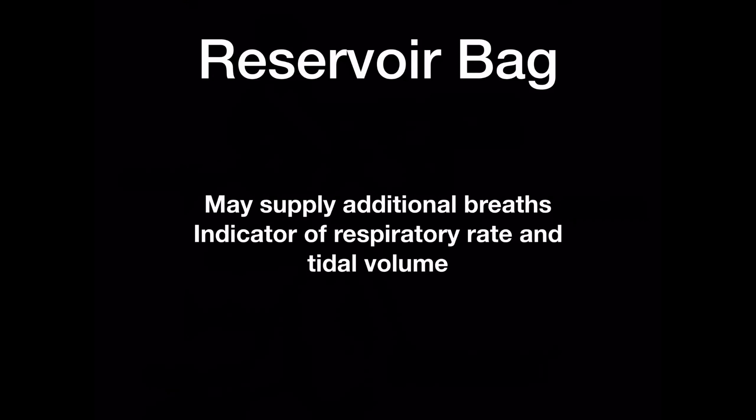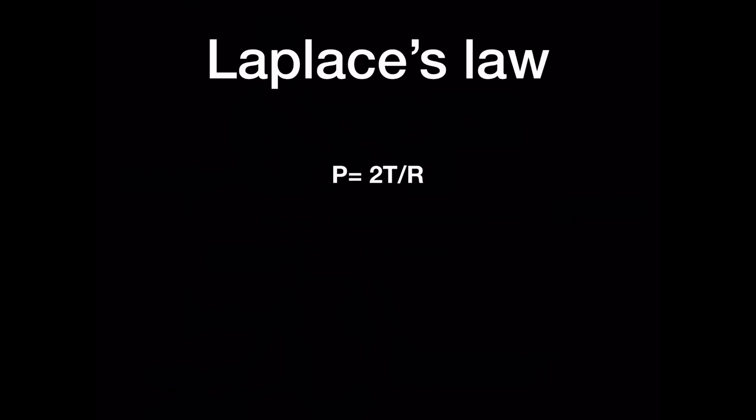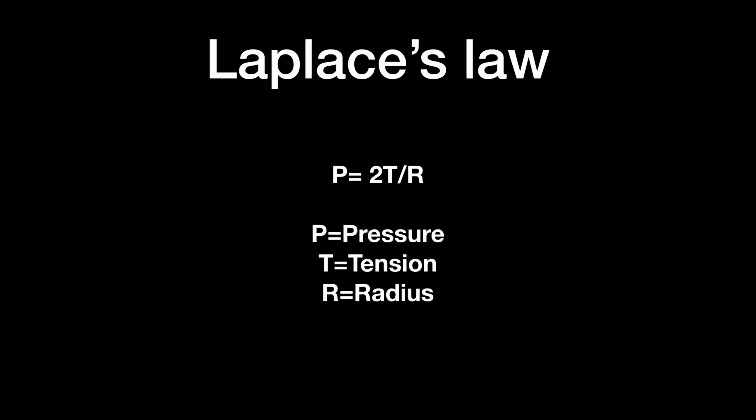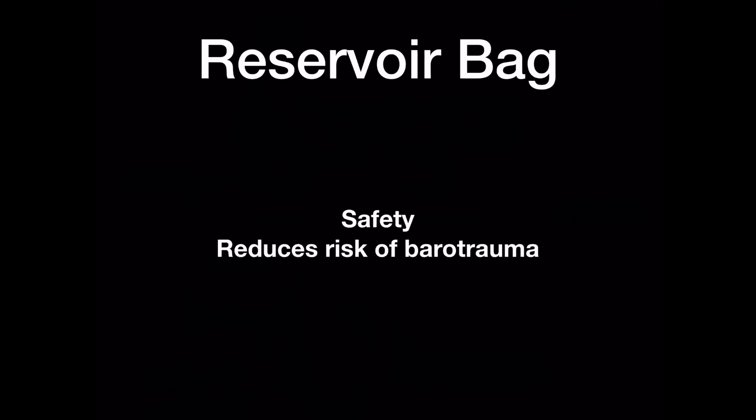The reservoir bag is a very nifty piece of kit. Due to Laplace's law, as the radius of the bag increases, the pressure reduces. This means that the bag is another safety method to reduce the risk of excessive transpulmonary pressures being delivered to the patient, and another way to reduce the risk of barotrauma.